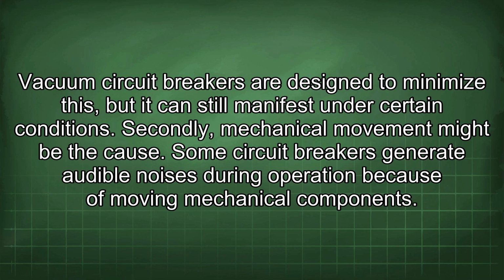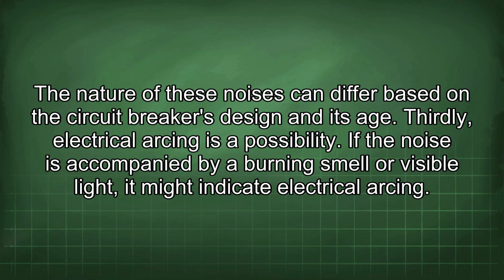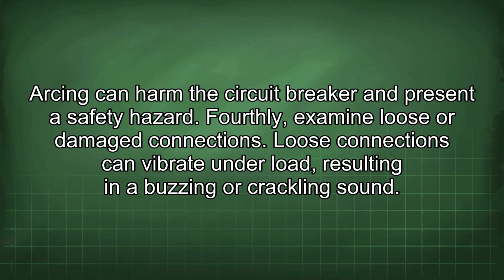Secondly, mechanical movement might be the cause. Some circuit breakers generate audible noises during operation because of moving mechanical components. The nature of these noises can differ based on the circuit breaker's design and its age. Thirdly, electrical arcing is a possibility. If the noise is accompanied by a burning smell or visible light, it might indicate electrical arcing. Arcing can harm the circuit breaker and present a safety hazard.